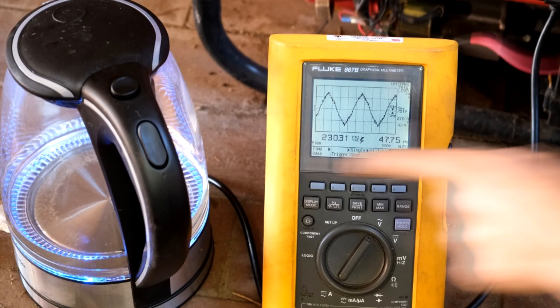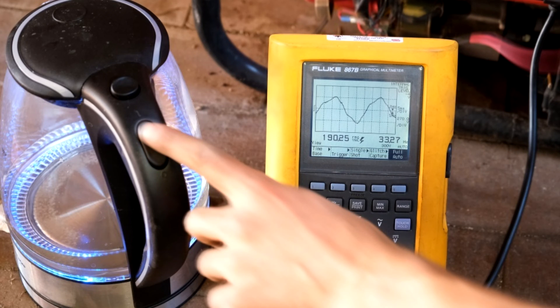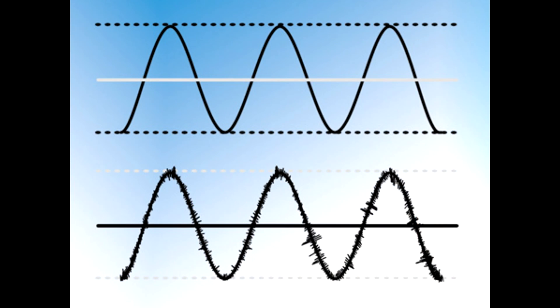Now that you've got that background, you can see what I'm talking about: there's a very dirty waveform, not quite sinusoidal, almost triangular, but the voltage and frequency are quite close to the goals of 230 volts and 50 hertz. But now look when I load the generator — it's 190 volts, the top and bottom of the waveform don't match, and that frequency is way out of specification. This generator should no longer be used.